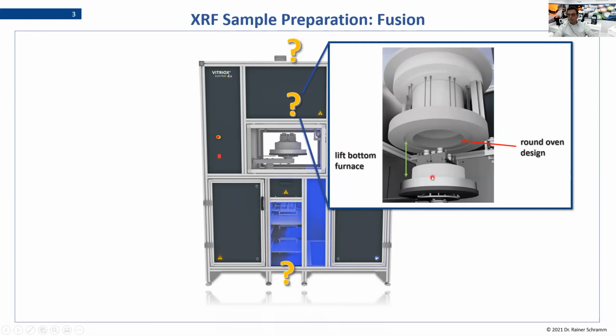And we have our lift-bottom furnace. That means that the door is the bottom, so we open to the downside, and in this way we lose much less heat when we open the furnace than you know from a classical muffle furnace principle. So this all leads to higher precision and higher accuracy in making fused beads and X-ray fluorescence analysis, and this is the design you need to do that.